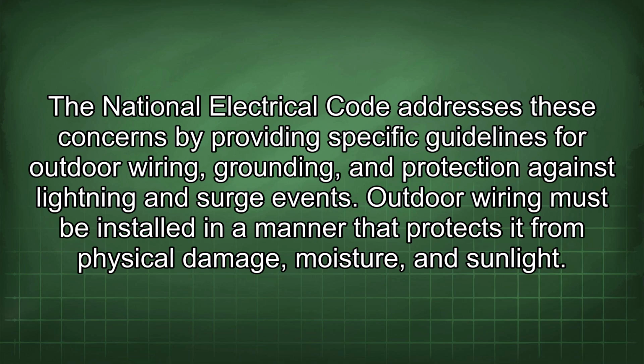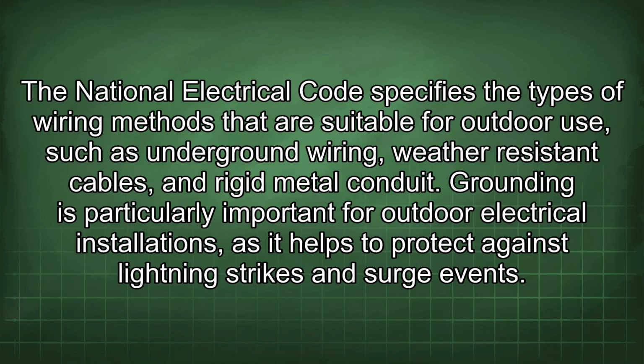Outdoor wiring must be installed in a manner that protects it from physical damage, moisture, and sunlight. The National Electrical Code specifies the types of wiring methods that are suitable for outdoor use, such as underground wiring, weather-resistant cables, and rigid metal conduit. Grounding is particularly important for outdoor electrical installations, as it helps to protect against lightning strikes and surge events.